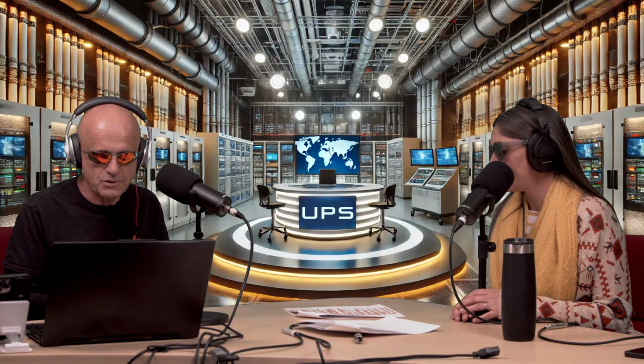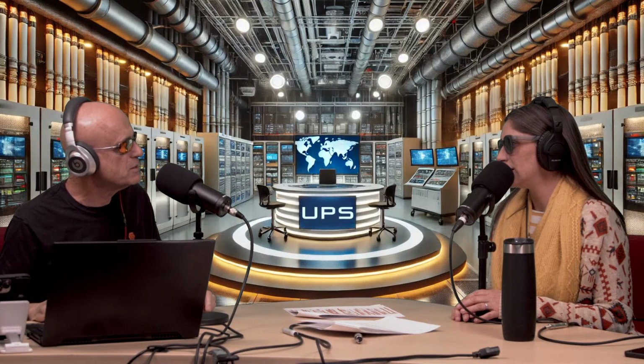Another thing to consider when getting a UPS is clearance issues and where it will be going. A common mistake is not checking whether the freight elevator can handle the weight of the UPS and battery cabinets up to, say, the 27th floor of a high rise. In some cases the answer is no. In those cases, we remove the batteries from the cabinets if it exceeds the load rating of the elevator. That's what our project managers are skilled at identifying - will we be able to get that UPS to your location.